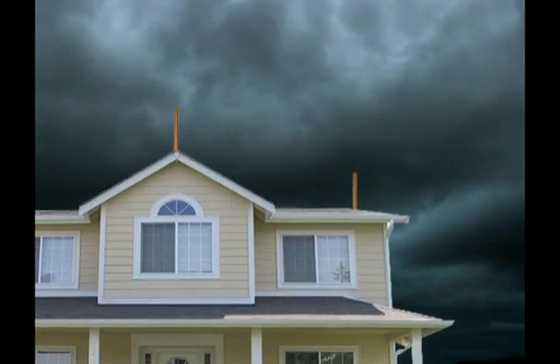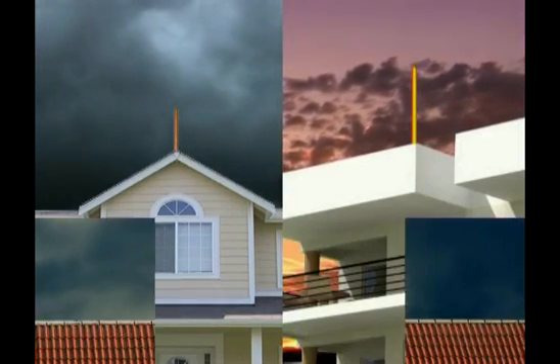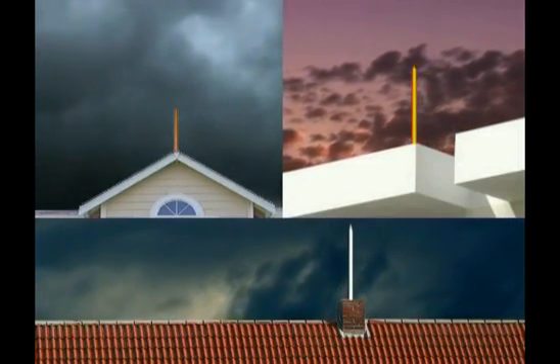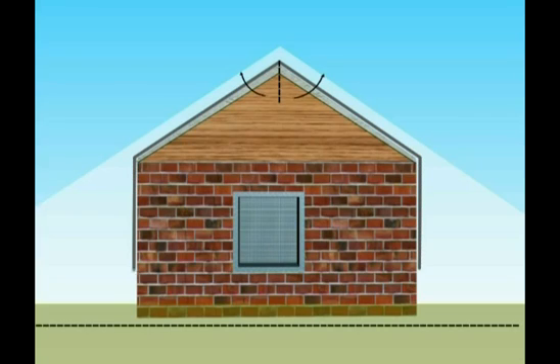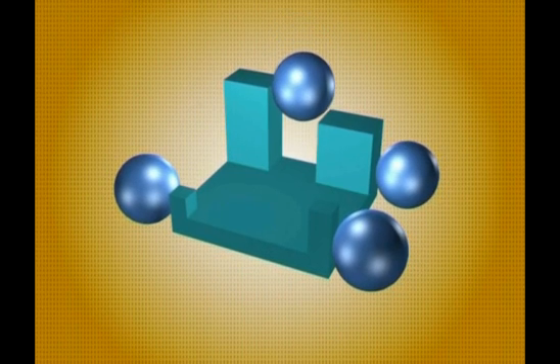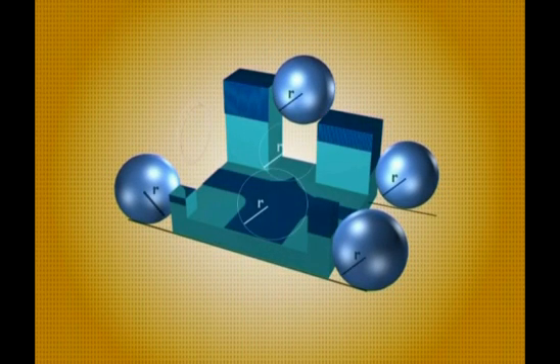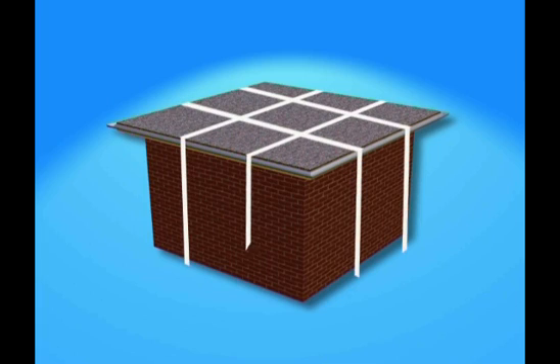There are three methods by which the air termination system can be installed, taking the building's shape and structure into consideration. For houses with simple shapes, the protection angle method can be adopted. The rolling sphere method is suitable for buildings of any shape. For houses with flat roofs, the mesh method can be adopted.